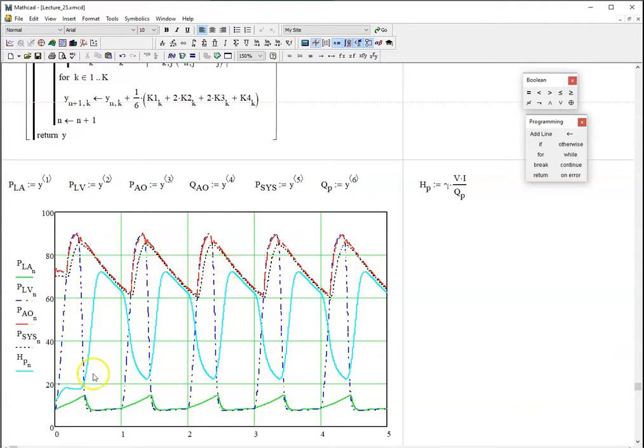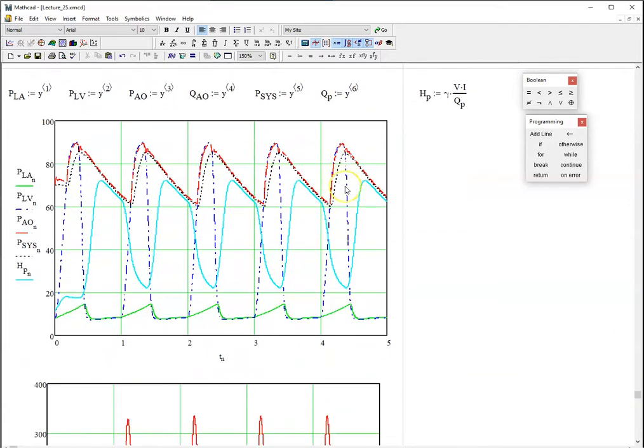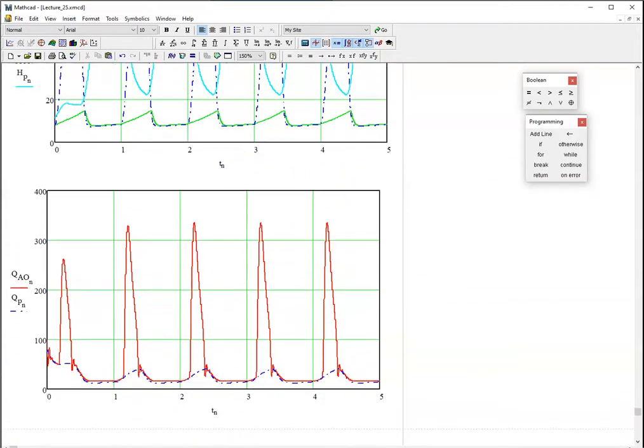Now, the LVAD is also producing head gain, and therefore it will be producing some flow, QP. If we plot the flows, the aortic flow and the pump flow, notice that most of the flow comes from the heart itself — that's the difference between the red line and the blue line. So this peak here, when the aortic valve is open, is what the heart is actually producing. What the pump is producing is under the blue line.